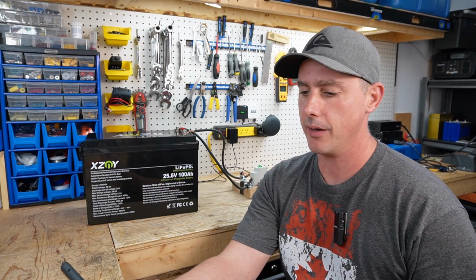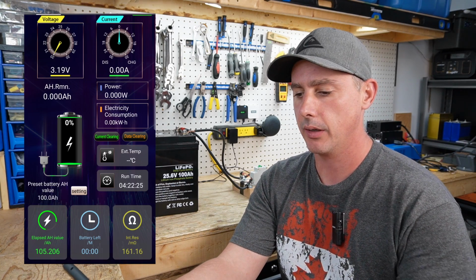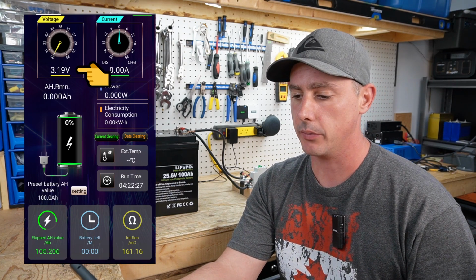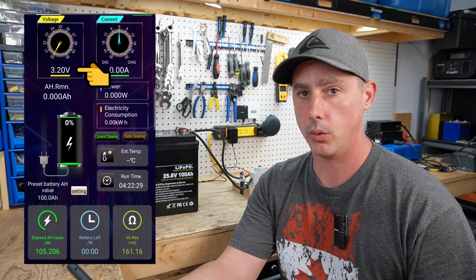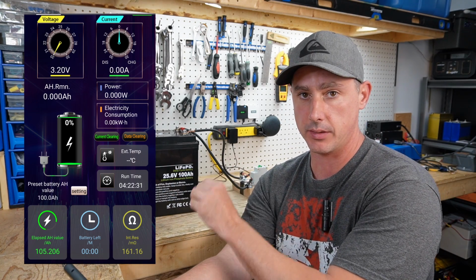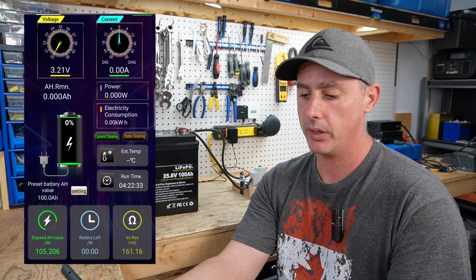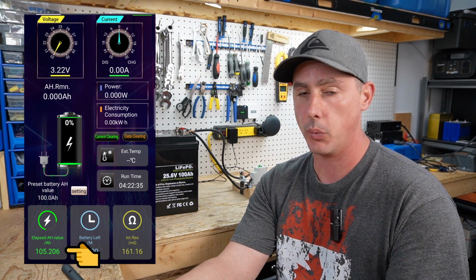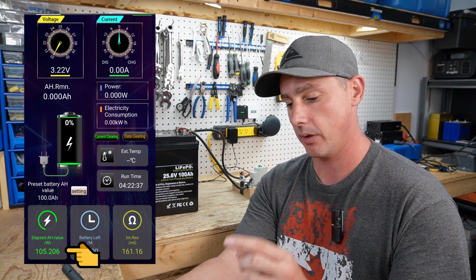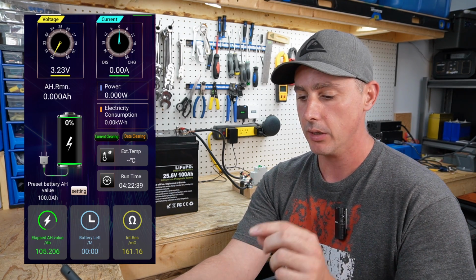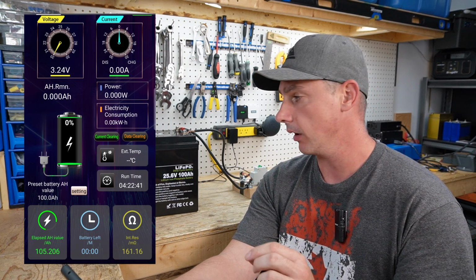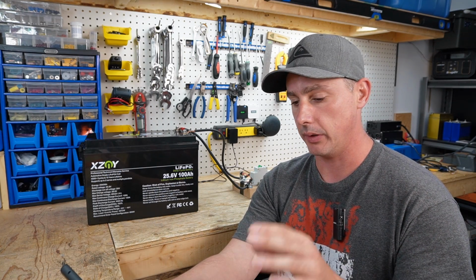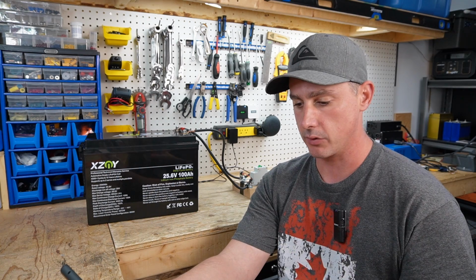All right, we have hit low voltage disconnect. As you can see, my volts are at about 3.19 volts. That's because the BMS has disconnected. And we are sitting at 105.206 amp hours out of a 100 amp hour battery. So we are above the capacity, and this tested all the way through. We did not get a hiccup, it just went all the way through.